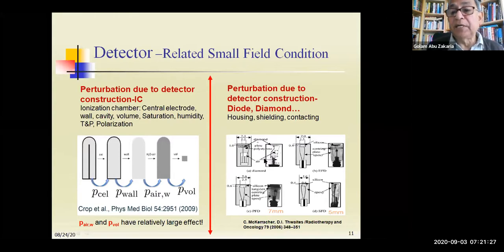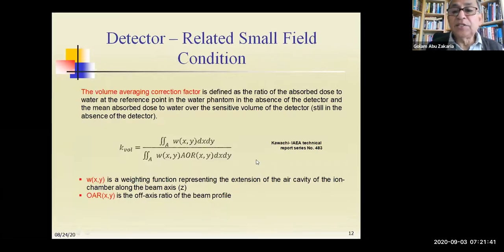So I suggest every medical physicist, before starting small field dosimetry, should see the internal structure of every detector. Otherwise, you make mistakes in the dosimetry. So there is a relation given by Kawachi. This is a very good relation where you can calculate the volume averaging correction factors. This is actually from the measurement. You see from the measurement of the beam profile, and here the actual dimension of the cavity.